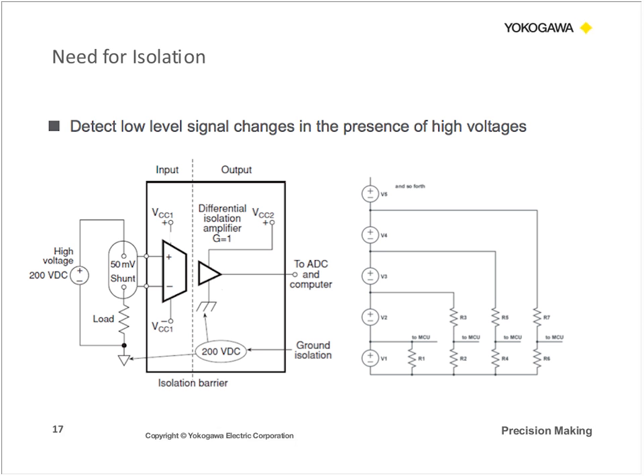All right, a couple more isolation cases. Let's say you need to measure low-level signal changes. So this could be a situation where you're working with shunts. For example, in that lower right corner picture, I have a system where we want to measure the voltage difference across a 50 millivolt shunt. But there's high common mode voltage, as you can see, between the circuit ground and the system ground. So there's 200 volts DC common mode voltage, and we only want to measure the 50 millivolt change. So how you're going to do this is through the use of isolation amplifiers, and we'll discuss a little bit more in detail how we can do that.